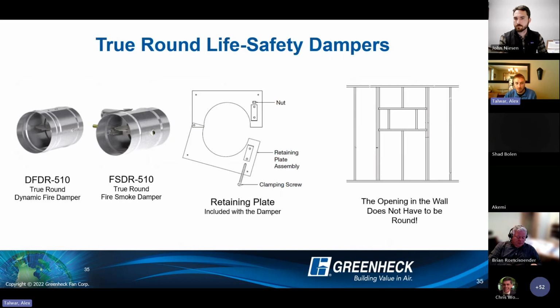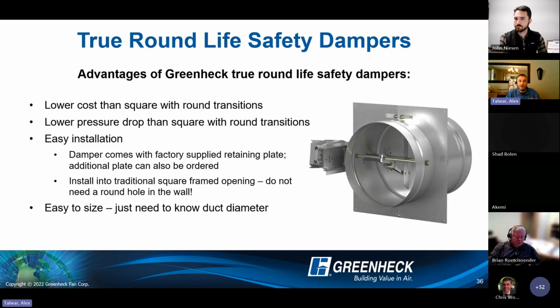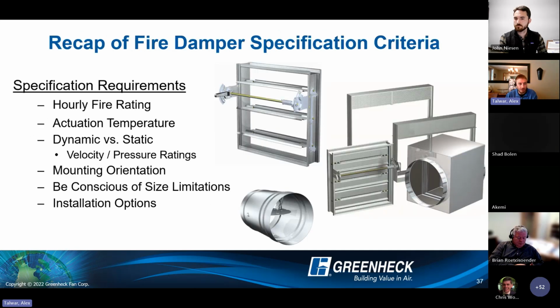Of course, if we do have round ductwork, instead of paying the extra cost for the square to round transition, you might want to consider just a true round style product. A lot of advantages to these products, typically lower cost, usually easier to install, and it doesn't need a round hole in the wall. It'll get framed the same way a square damper does. And it comes with the retaining plate, UL approved installation methods. So a lot of advantages, and usually better pressure drop too. So a lot of advantages to the true round style products if you have round ductwork. There we go. I could have just gone to the next slide and saved my voice, but true round. We do have a video, I think, as well on the website if you're interested in learning more about those products. But yeah, a lot of advantages there.